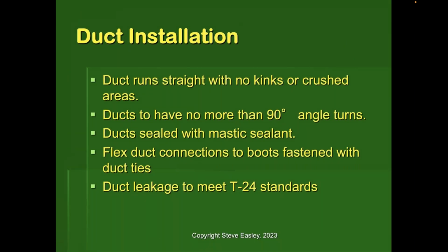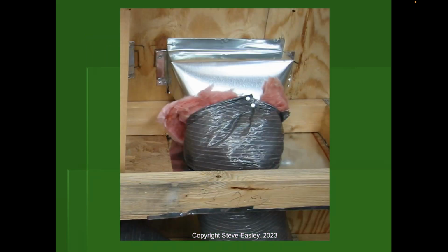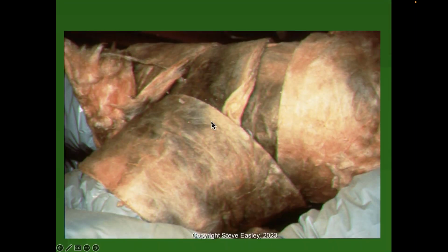Obviously, these things are important. So duct runs should be straight with no kinks or crushed areas. They should have wide-angle sweeping turns with, I believe, metal elbows, obviously sealed with mastic sealants, flex duct connections, the boots with duct ties and the appropriate tape, and duct leakage. Always meet your local standards; the new codes now are doing a much better job of requiring that we eliminate duct leakage. Here, for example, they just put a couple of sheet metal screws. There's no air sealing where the boot to floor connection meets. There's no air sealing that takes place where this duct is. Again, example, the dirty insulation.